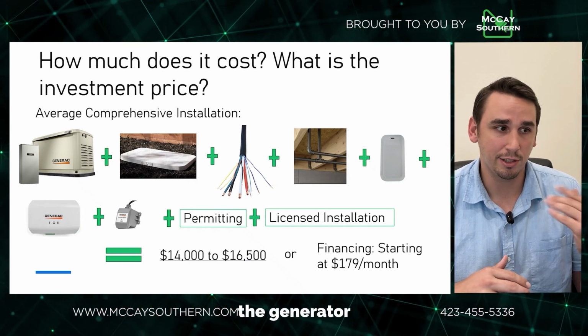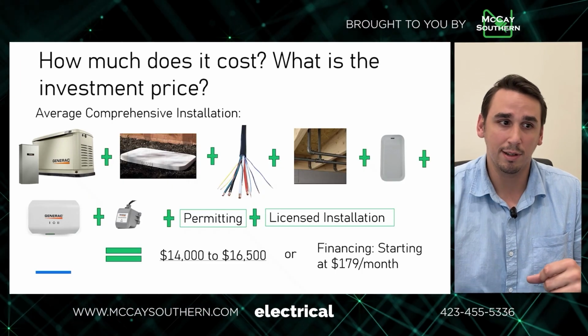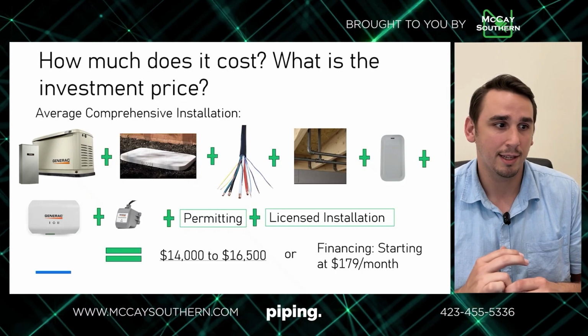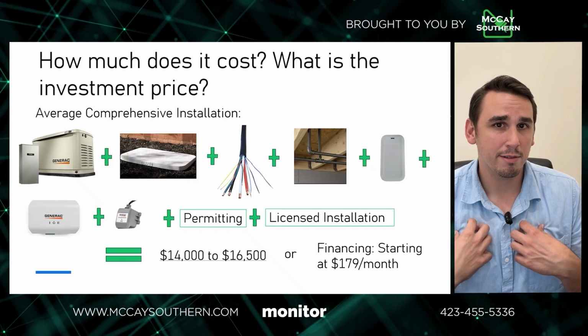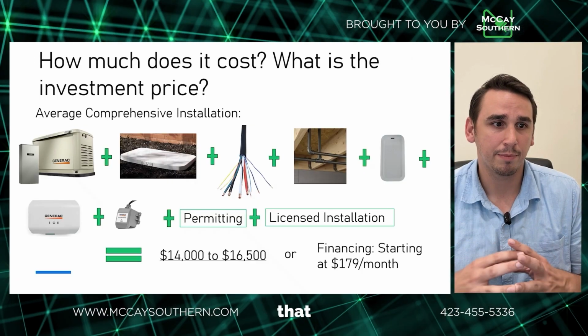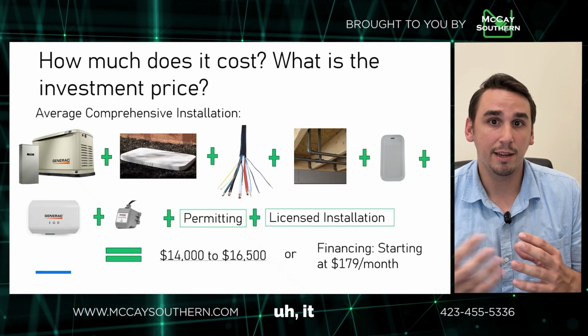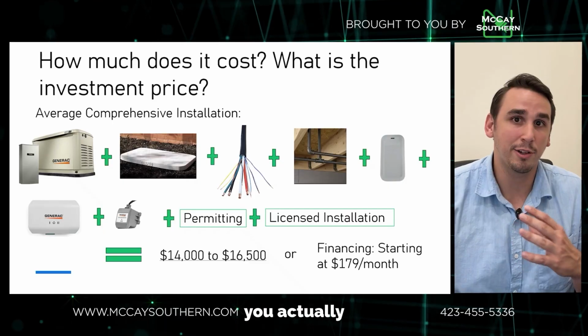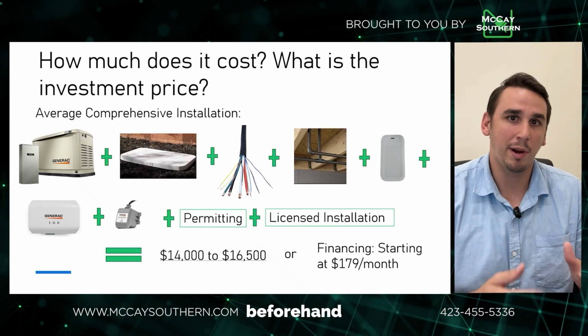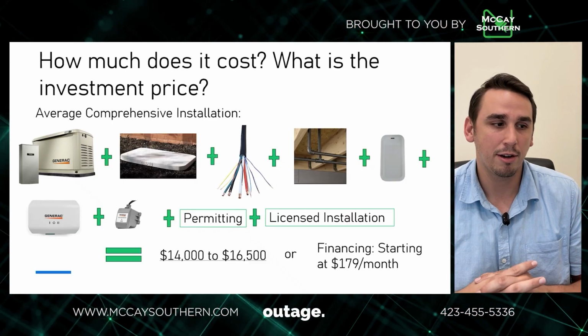So obviously you've got the generator itself, the platform for it, electrical wiring, and gas piping. We always put a 4G monitor on our generators to make sure that if there is an issue, it notifies us and we can correct it before you actually need the generator. We like to find out beforehand if there's a problem, not during a power outage.